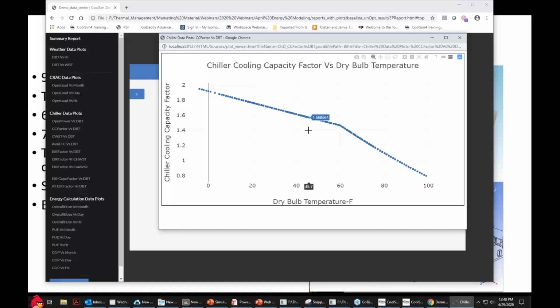We did have another question that came in, Henry, about where we got our weather data. The weather data is typical meteorological year data, TMY3 data, that we had processed to just extract the dry bulb and wet bulb and humidity ratio characteristics of the outdoor air.